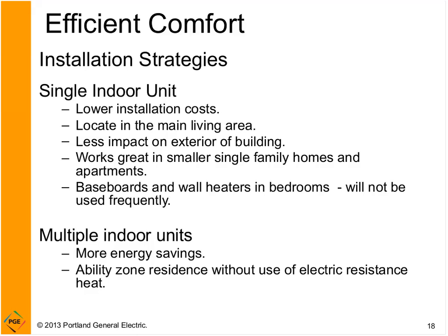I was involved in looking into an installation that had the baseboards disabled, and I did some temperature monitoring, and I found that the temperature didn't vary that much. This was probably a 750 square foot apartment unit, and the temperature really didn't vary that much between the bedrooms and the space where the single head ductless heat pump unit was located. Multiple indoor units is something that you could consider. There's the potential for more energy savings because you're able to zone the residence without the use of electric resistance heat. But again, for a small apartment, probably not necessary.